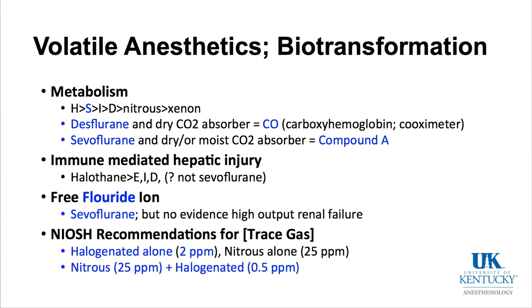The National Institute of Occupational Safety and Health in the United States makes recommendations for trace gas concentrations. If you're using isoflurane, sevoflurane or desflurane alone, 2 parts per million is the high-end recommendation. Don't exceed that. Nitrous alone, 25 parts per million. And when nitrous and the halogenated agent are combined together, the level of the halogenated agent is only supposed to be up to 0.5 parts per million. A take-home point: if you can smell your inhaled volatile anesthetic like sevoflurane or desflurane in the operating room, you are way, way, way above these NIOSH recommendations.